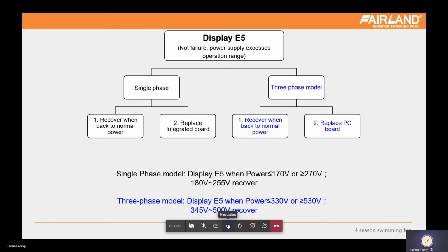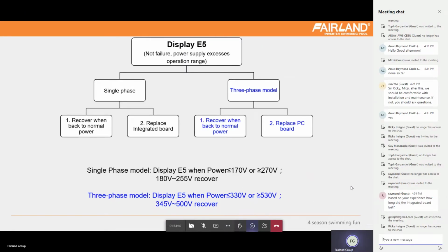E5 is also not a failure, but a power supply exceeding the operation range. For single phase, the normal range is 180 to 255. In this range, the inverter unit can run normally. But out of this range, it will trigger the protection code E5. I think the voltage in your country should be more stable than in other places, so it is fine for you.